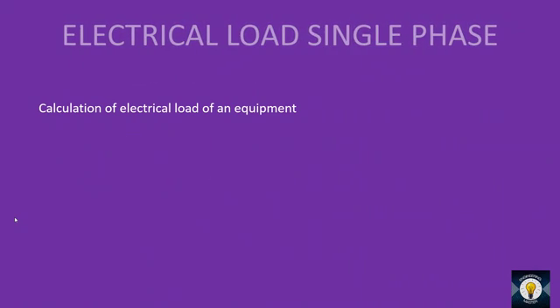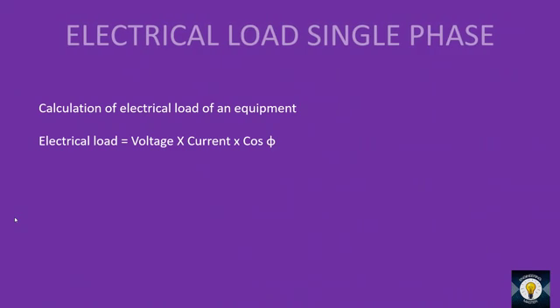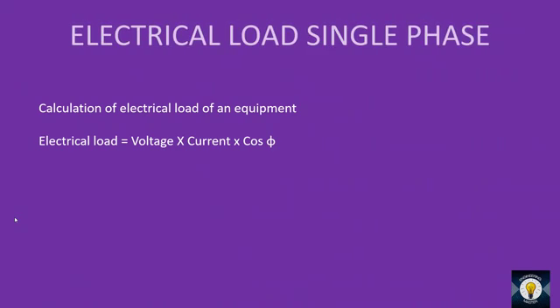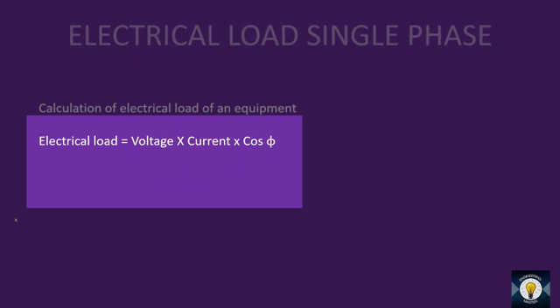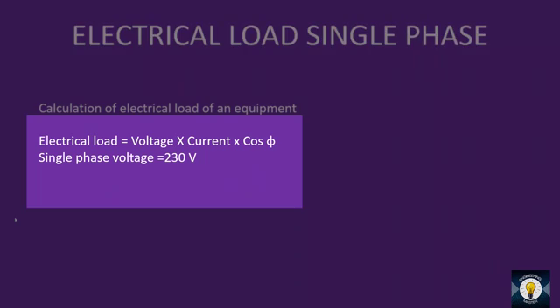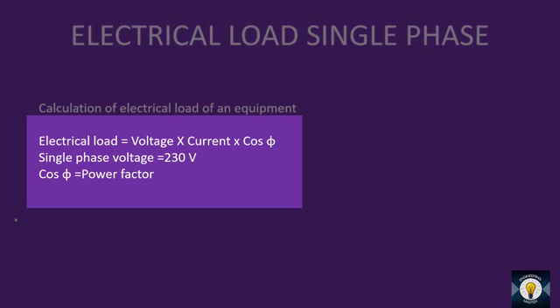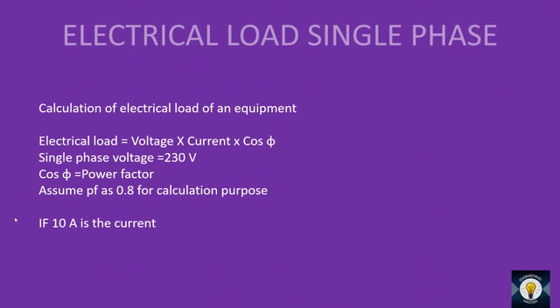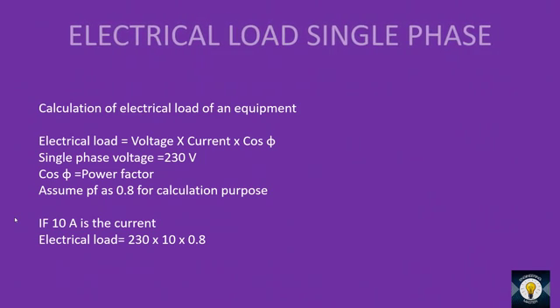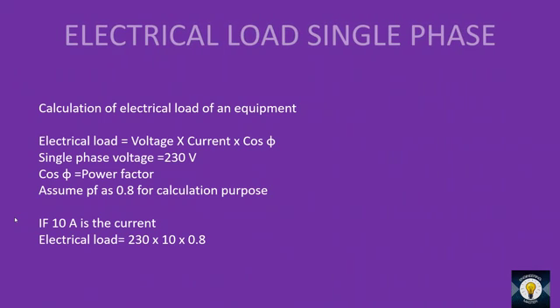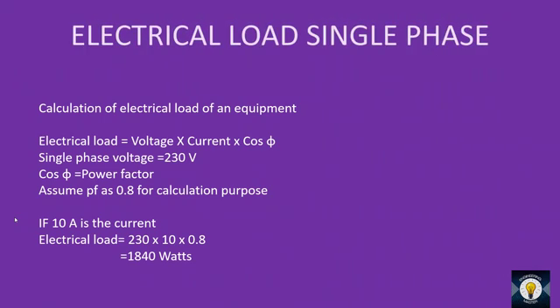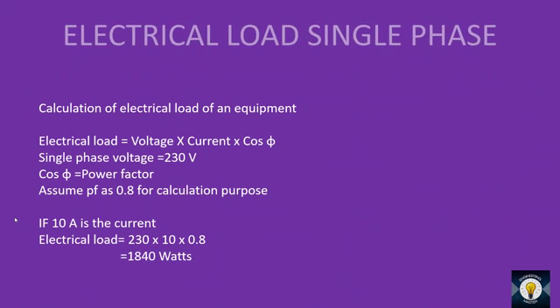If you want to calculate the electrical load of equipment, first identify whether it is single phase or three phase. If it is single phase, the electrical load equation equals voltage into current into cosφ. Single phase voltage is 230 volts. Current can be obtained from the nameplate. Cosφ is the power factor; for calculation purposes we assume 0.8. If 10A is our current, then electrical load equals 230 × 10 × 0.8 = 1840 watts, or 1.84 kilowatts.